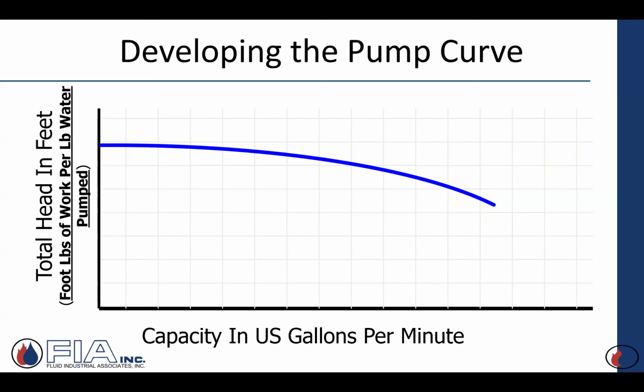But what you can take away from it is on the bottom, horizontal here, moving from left to right, this axis will always list our capacity and flow. And typically what we're going to be referencing would be gallons per minute, GPM. And then this axis, the vertical on the left-hand side, would be feet of head, typically, PSI or feet of head. So it's an expression of how much energy, how many foot-pounds of work per pound of water passes through the impeller, through that volute that we just talked about, that energy that the motor's spinning and the impeller's imparting velocity. How much energy, how much work have we applied? We'll get into better details with that, but that's the pump curve, flow versus head.